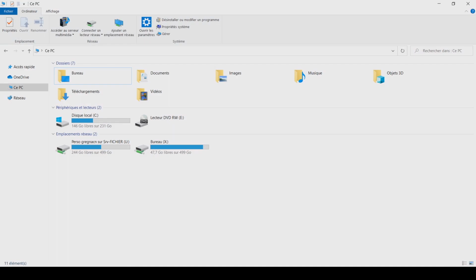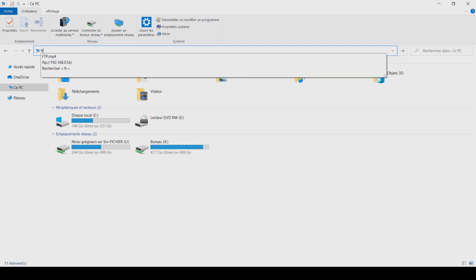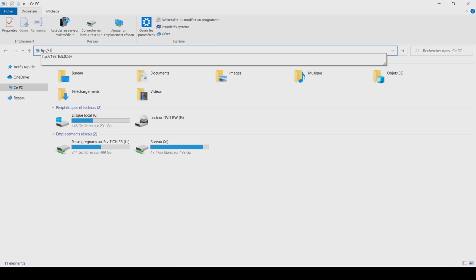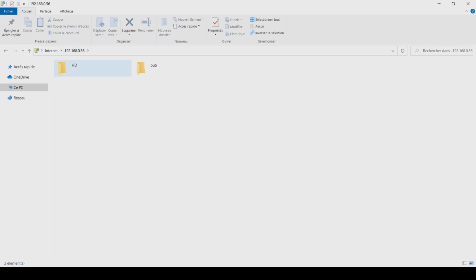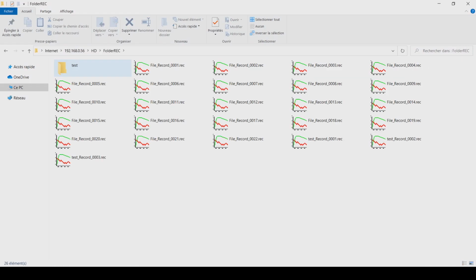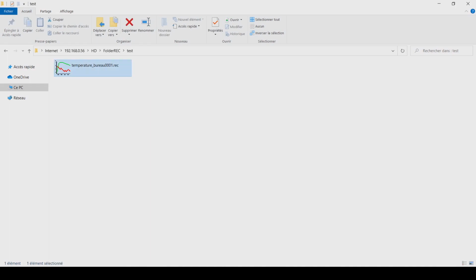The second one, a transfer via FTP server. To do so, the instrument has to be connected to a computer via an Ethernet cable or connected to a network via Ethernet or Wi-Fi. To download a recording via the FTP server, first go to your computer's Windows Explorer and type FTP:// and the IP address of the instrument. Access the internal hard disk of the instrument and then the recording folders. Select the folder and then the file you want to export. Make a copy of it to your computer's internal hard disk.